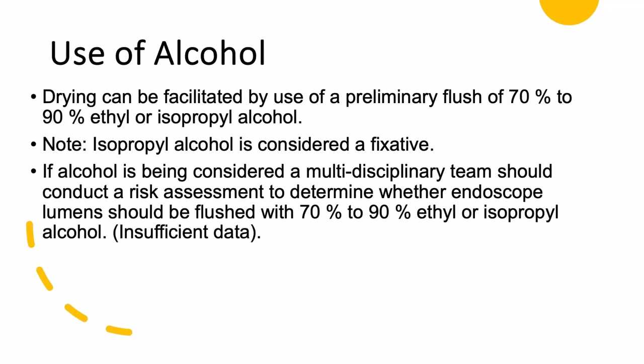Alcohol is another issue that is controversial right now. There doesn't seem to be enough data to substantiate the continued use of it. We know that drying can be facilitated when we use a flush of 70 to 90% ethyl or isopropyl alcohol. But the issue is that isopropyl alcohol is considered a fixative. So if you have any microorganisms there, they're going to be fixed and difficult to remove. So if you want to continue to use alcohol, again, this would be something your multidisciplinary team should conduct a risk assessment.